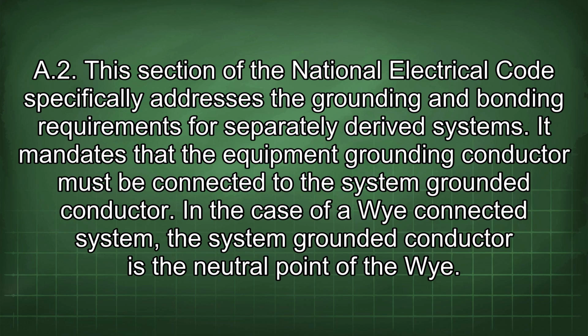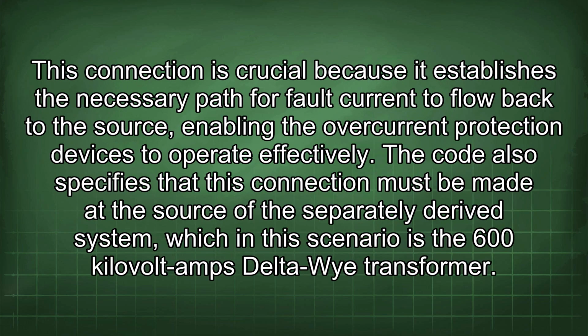It mandates that the equipment grounding conductor must be connected to the system grounded conductor. In the case of a Y-connected system, the system grounded conductor is the neutral point of the Y. This connection is crucial because it establishes the necessary path for fault current to flow back to the source, enabling the overcurrent protection devices to operate effectively. The code also specifies that this connection must be made at the source of the separately derived system, which in this scenario is the 600 kVA delta-Y transformer.